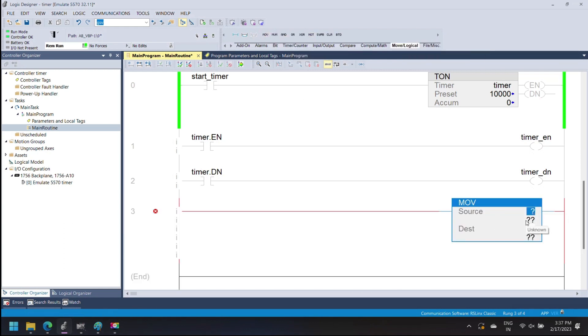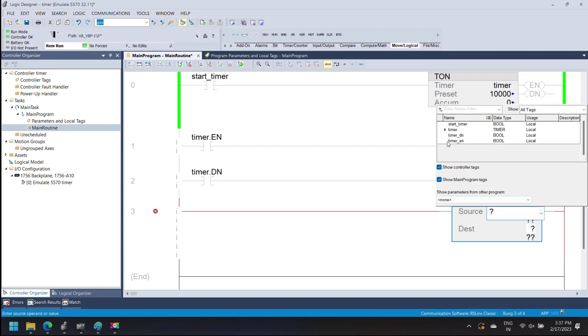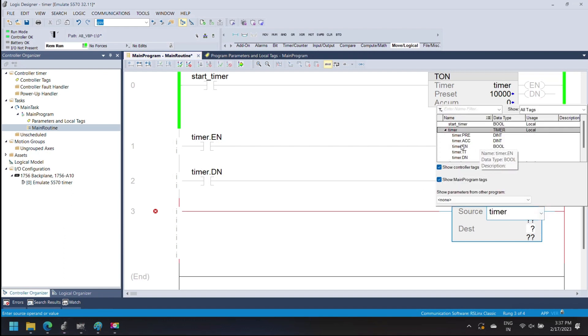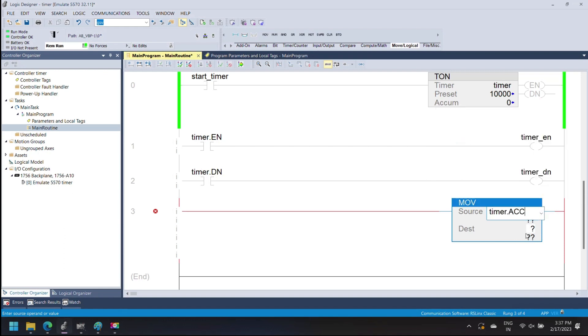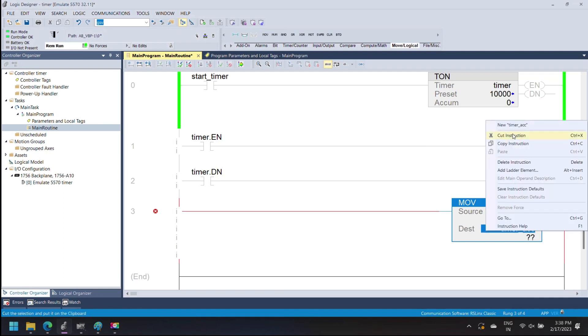In this rung I am adding a move instruction to move the timer accumulator value to a new tag for another operation. The data type for the timer accumulator value is DINT, so when you move the timer accumulator value to a new tag, always use the DINT data type for your tag.